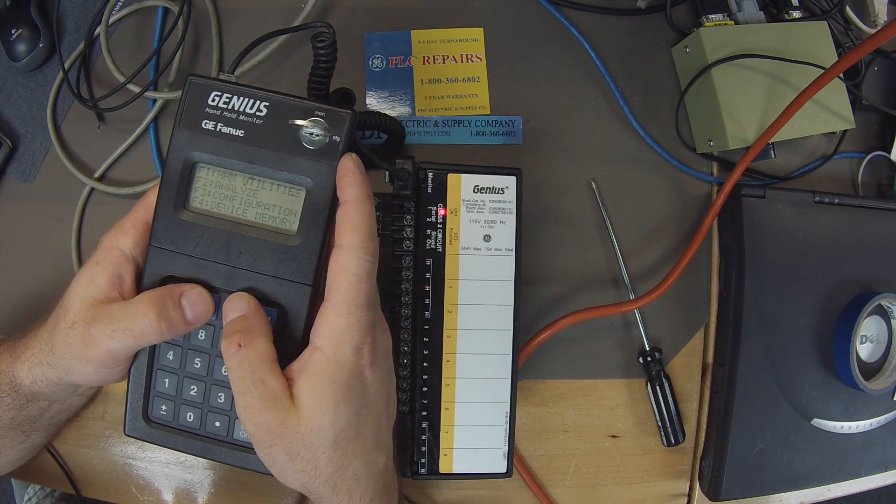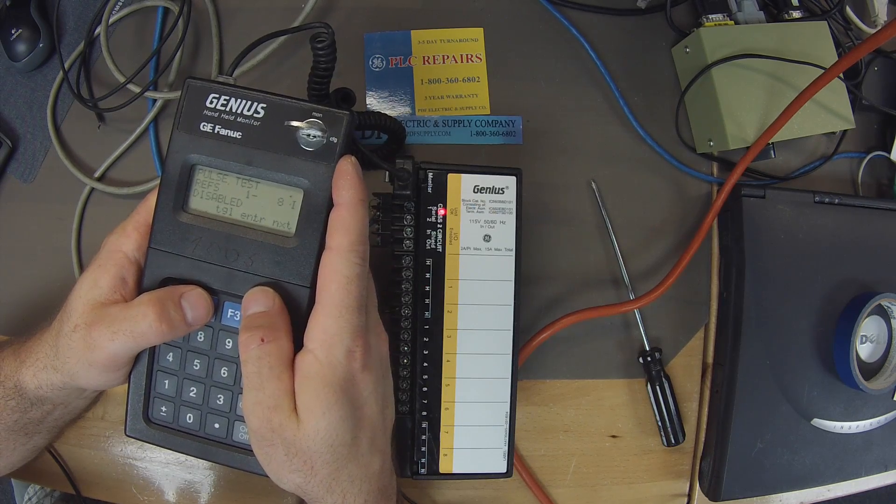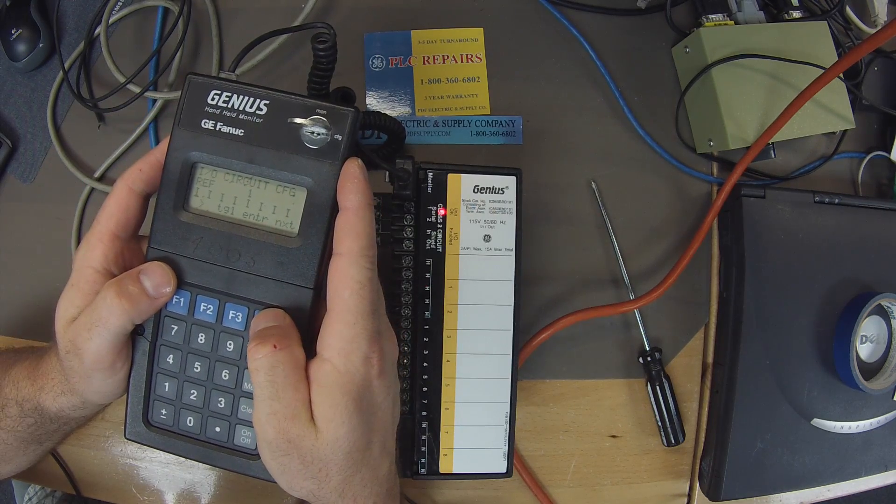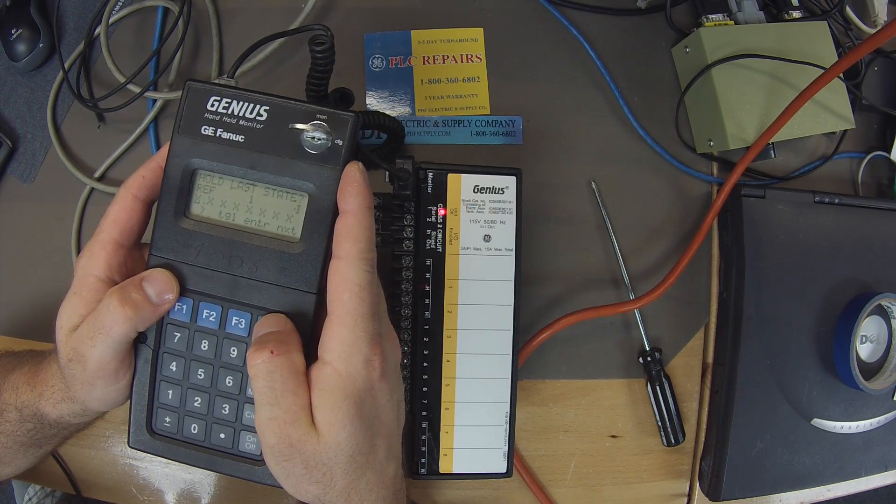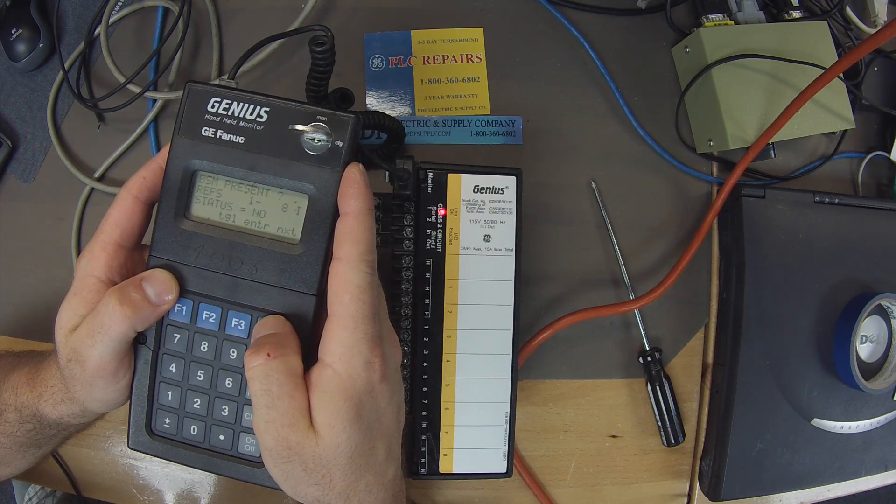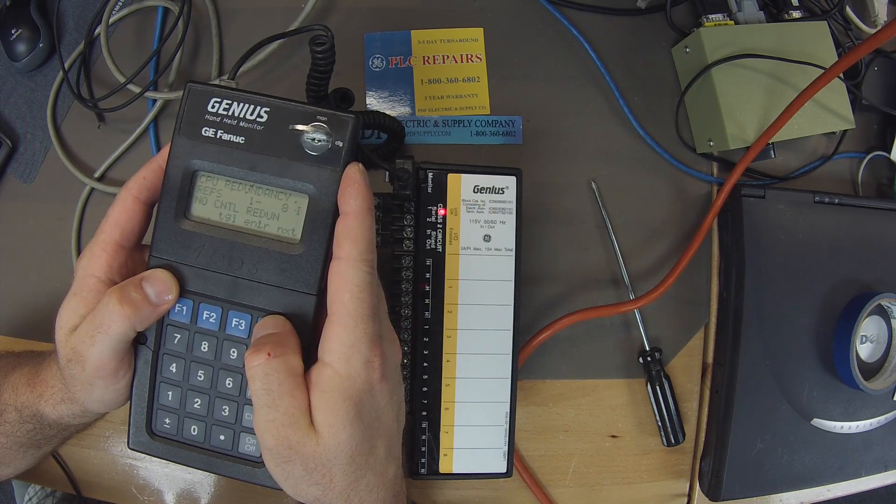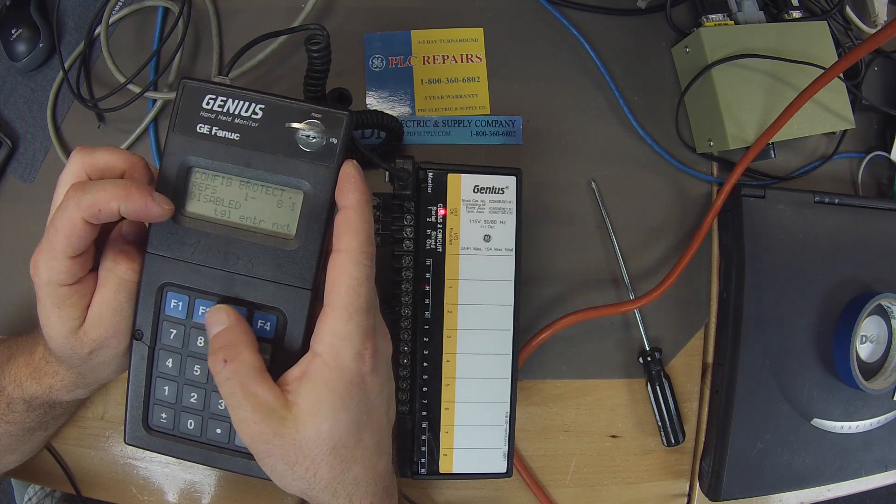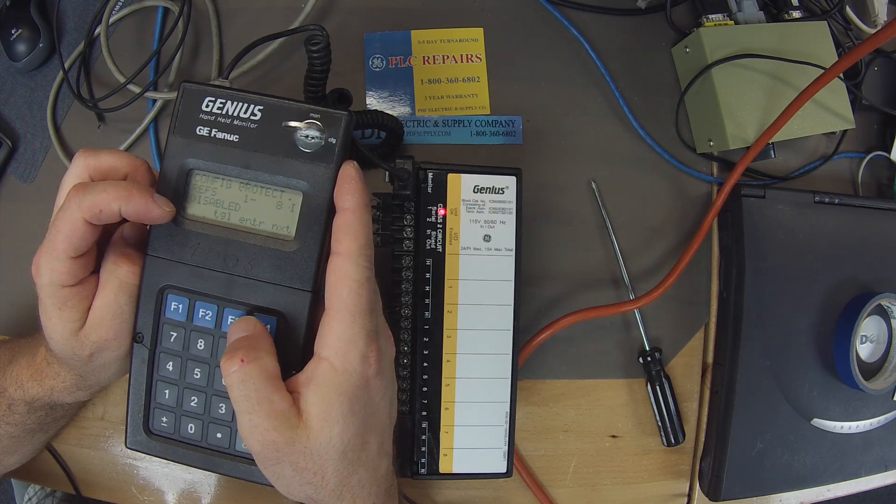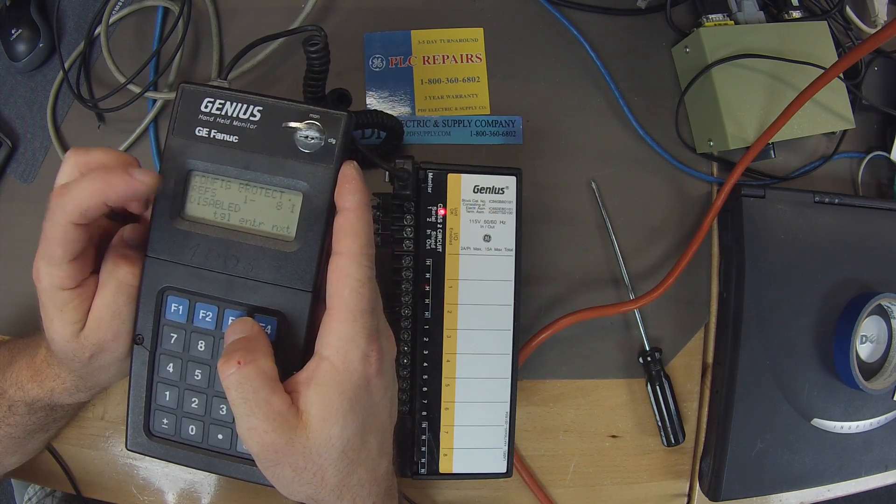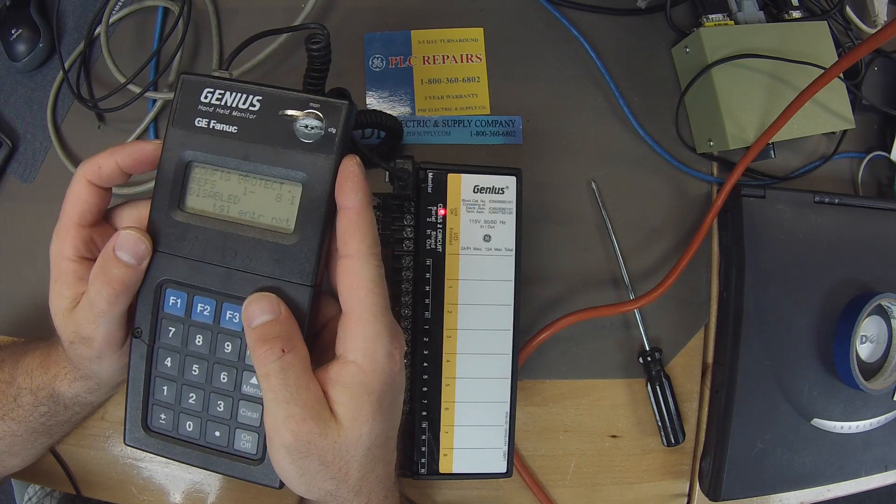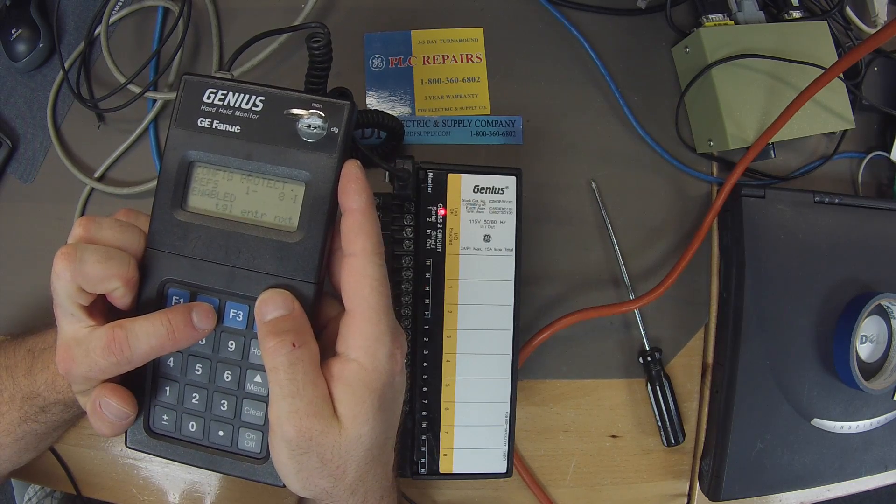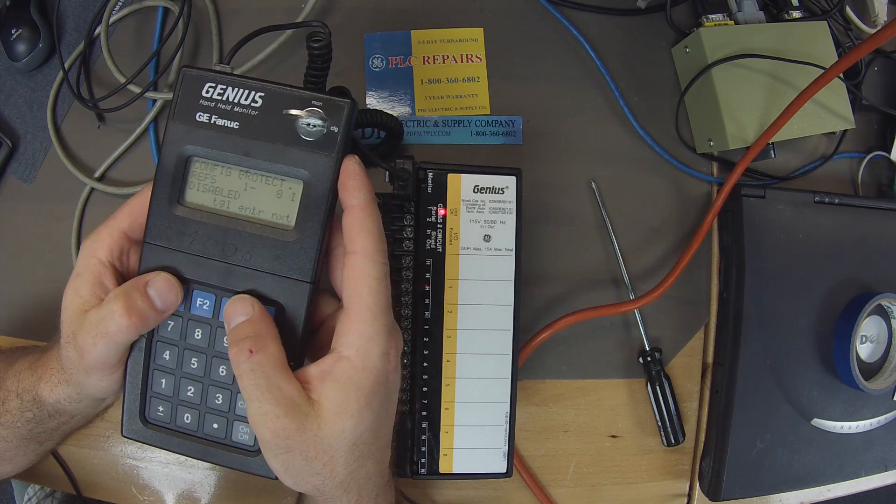Go back to home, F3 configuration, F2, configure block. Now we want to make sure that our settings are set up so that it doesn't inhibit the test. The other thing is this configuration protect, you're not allowed to edit or make any changes to the programming of the genius block unless this is in the disabled function. However, if you do need to have it set up a certain way, you need to protect your block, you can always toggle to enable the protection. But in this particular case, as we're testing, we're going to leave that alone.